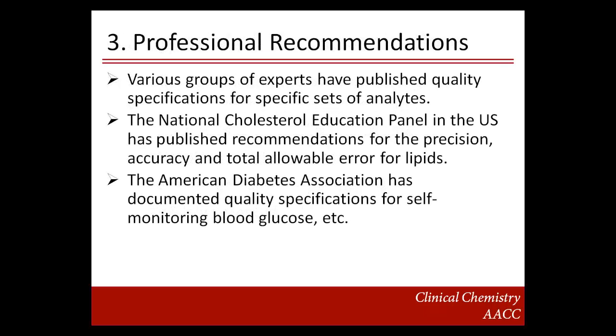The third quality specification in the hierarchy is from professional recommendations. Various groups of experts have published quality specifications for specific sets of analytes. The National Cholesterol Education Panel in the U.S. has published recommendations for precision, accuracy, and total allowable error for lipids. The American Diabetes Association has documented quality specifications for self-monitoring blood glucose.